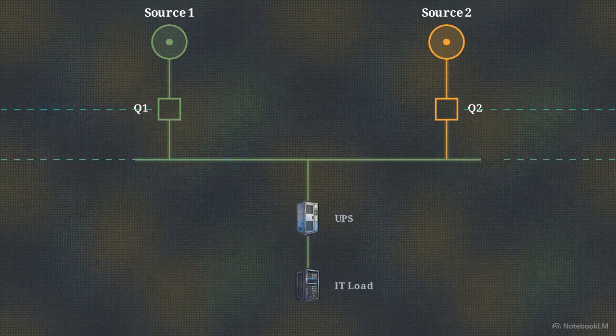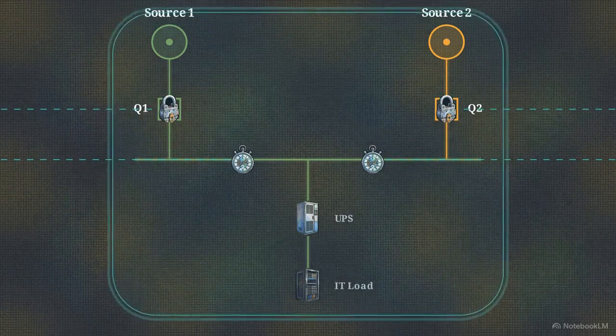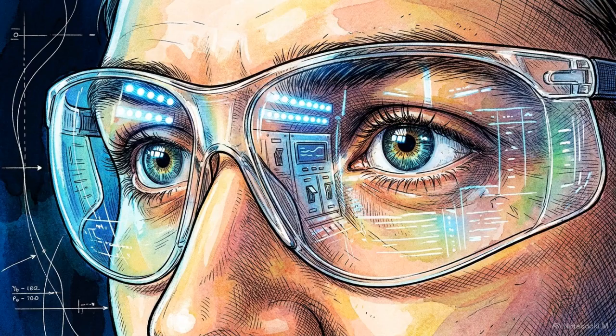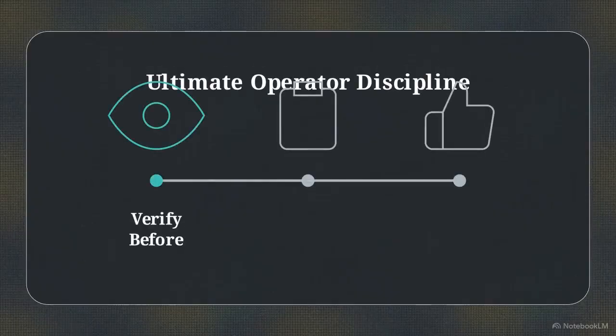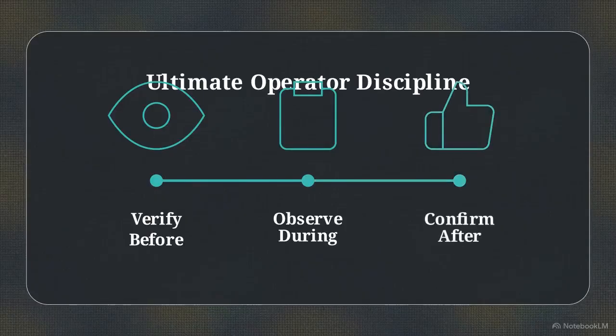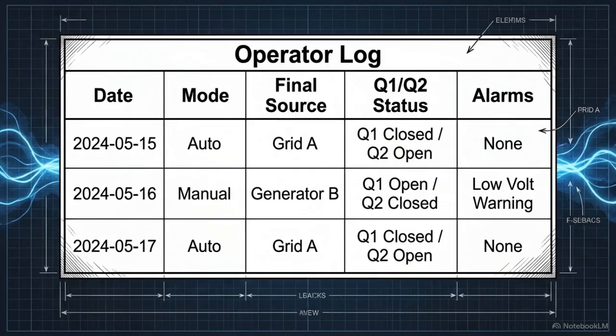Every timer, interlock, and logic sequence programmed into the ATS exists for one specific purpose: to preserve the physical integrity of the facility's single-line diagram. The ultimate operator discipline required to support this architecture is strict. Verify before, observe during, and confirm after every single transfer. Execution is only half the job. Comprehensive logging of final breaker states, source conditions, and alarm history is required for troubleshooting and operational accountability.